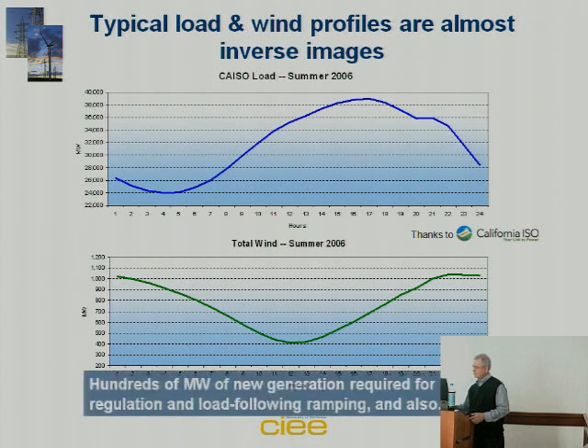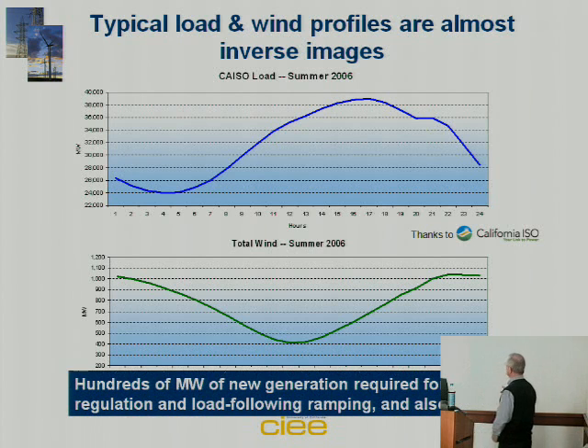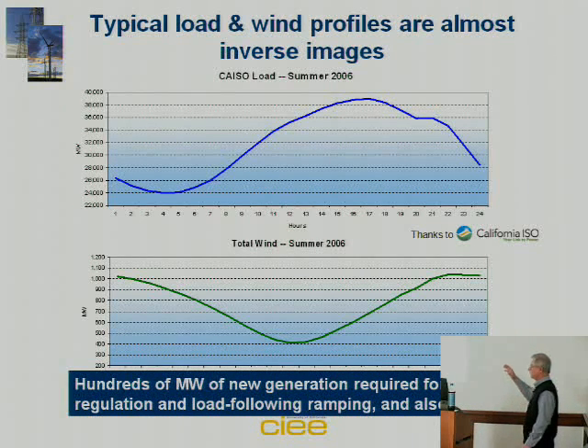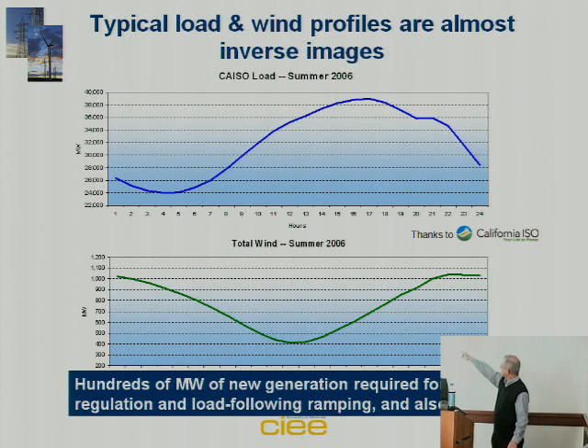One issue has to do with regulation and load following. Assuming we had a lot of wind on the system, which someday we plan to, if you have a lot of wind at night and as morning comes and load picks up because customers start using more, but your wind is falling off, you get a double whammy—generation falling off just as load is picking up. So there's a much more rapid ramp rate than we're used to, which raises some concerns.